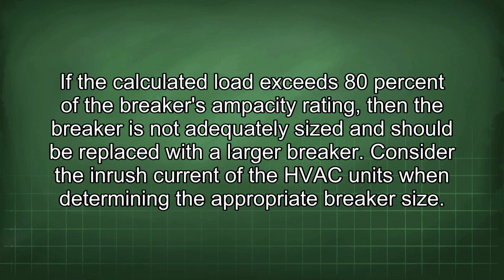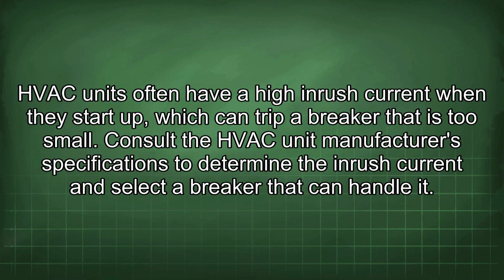Consider the inrush current of the HVAC units when determining the appropriate breaker size. HVAC units often have a high inrush current when they start up, which can trip a breaker that is too small. Consult the HVAC unit manufacturer's specifications to determine the inrush current and select a breaker that can handle it.